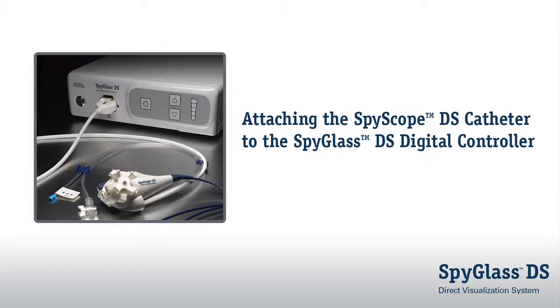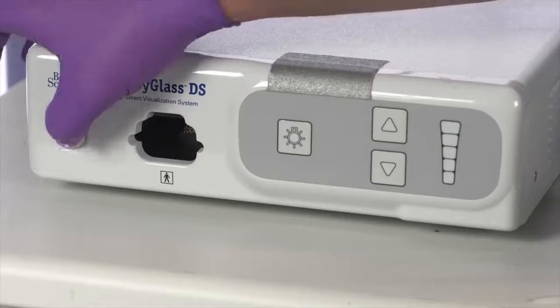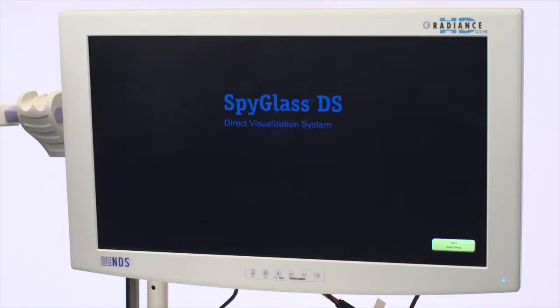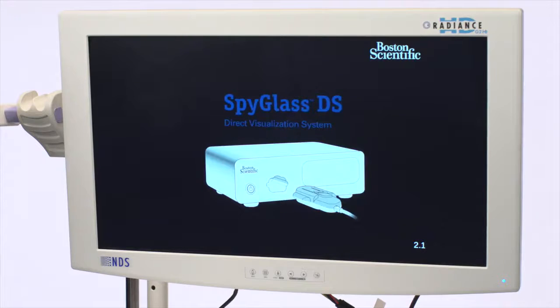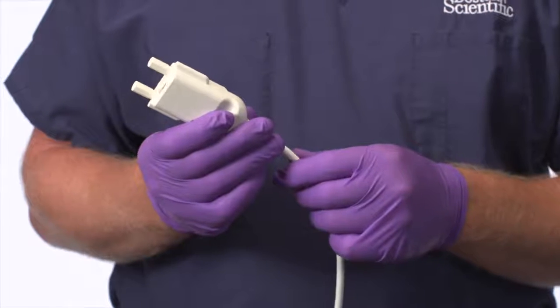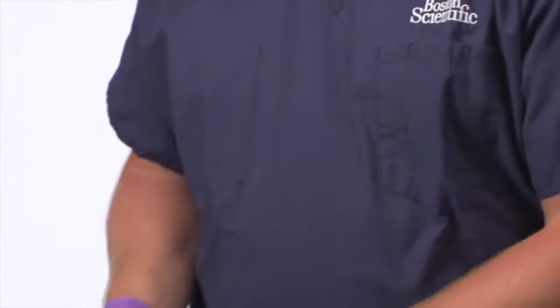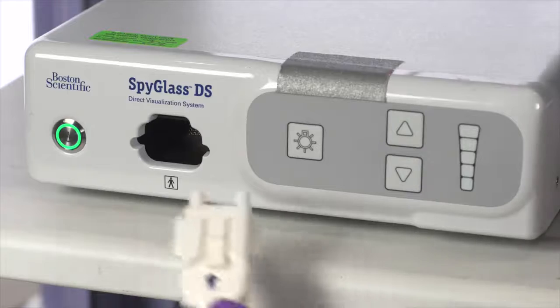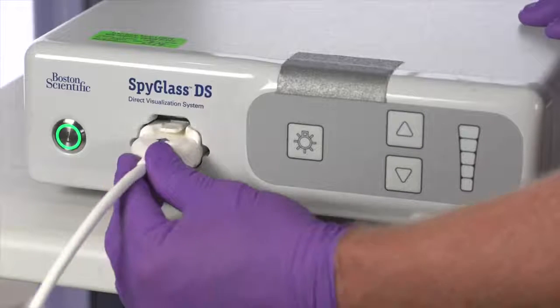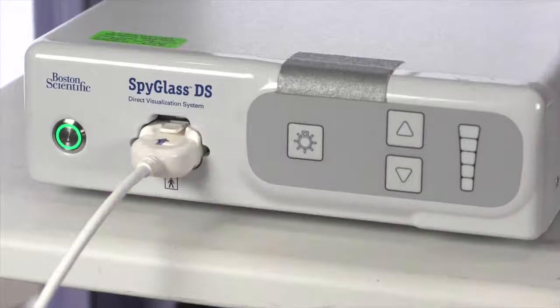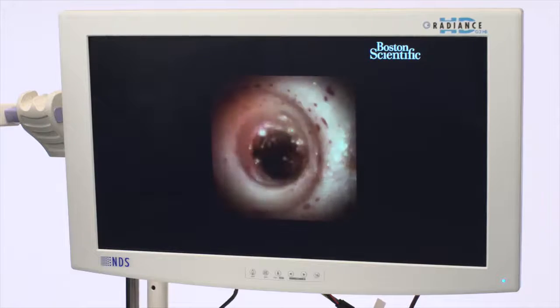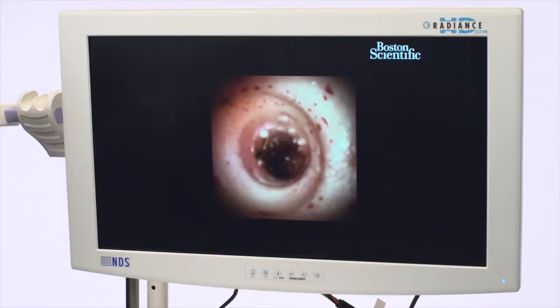Attach the SpyScope DS catheter cable to the SpyGlass DS digital controller and adjust the image following these steps. Power on the controller. When the monitor used with the controller displays the Cable Connect screen, plug the SpyScope DS catheter cable connector, locking tab facing up, into the receptacle on the front panel of the controller. Push the cable connector in until the locking tab engages. Verify an image is present on the screen.